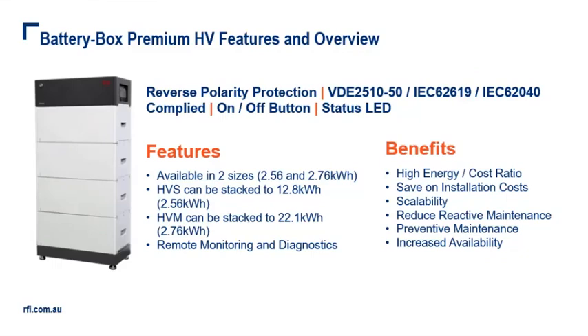This is the high voltage BYD product, with two sizes: the HVM and the HVS. Previously we only had one size, but I'll get to that in the next couple of slides. A single HVM stack gives 22.1 kilowatt hours of storage, and you can parallel 3 stacks for a total of 66.2 kilowatt hours. Compare that to the HVS: a single stack is 12.8, paralleled up to 38.4. The key difference between the HVM and HVS is essentially the module-level energy storage capacity - the HVS is 2.56, the HVM is 2.76.